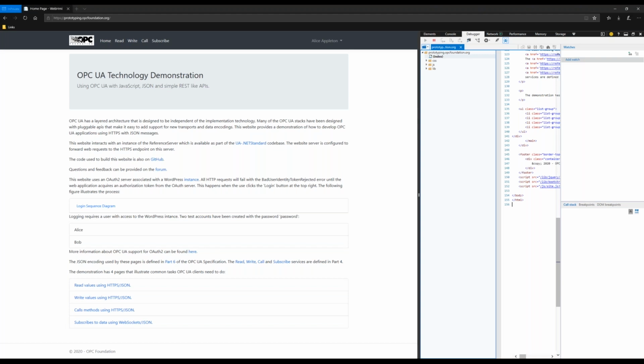Can I add nodes dynamically? This is a very common use case for methods. What happens is people will define methods with the purpose of adding nodes dynamically. So for example, if you wanted to add a new controller to an area within your Opc Ua server, you would have an add controller method, and you would call that, and you could use the REST interface to invoke that method, and then that would cause all the new nodes to appear.